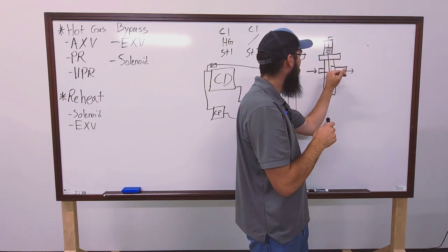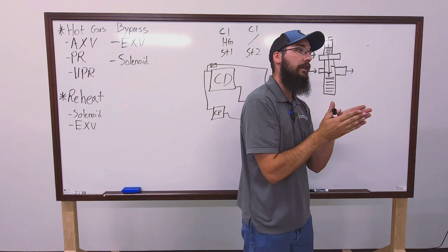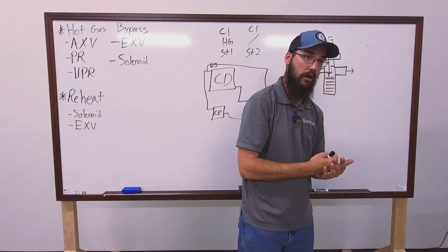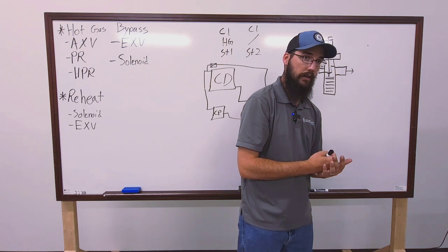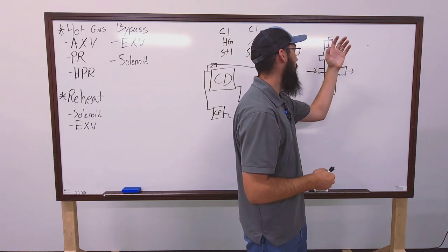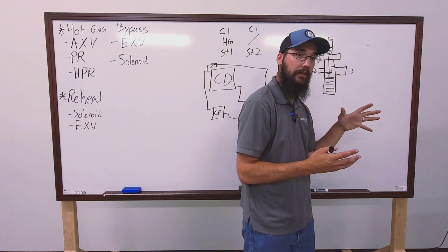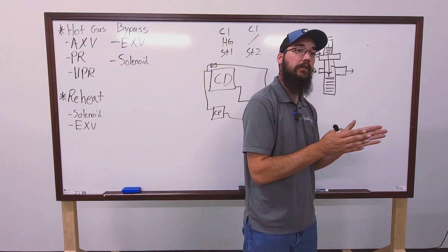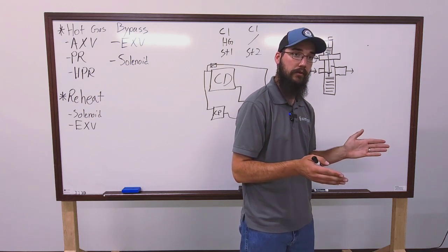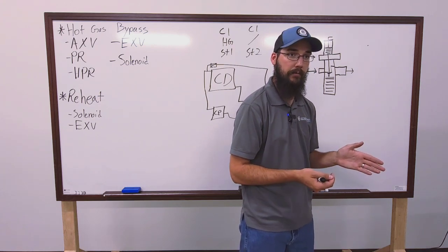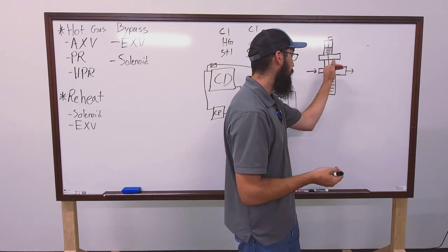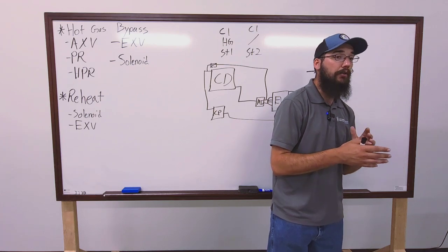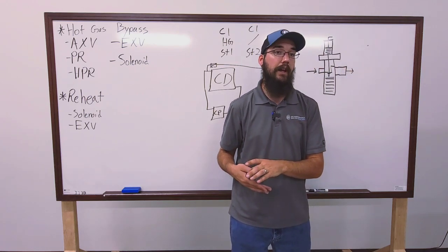So, ultimately, the more you push this down, so the more you thread the adjustment ring in. So, the more you load the springs? Yeah, there you go. The more you load the springs, the higher, or the lower the DP, the pressure differential you'll create across. And, the more you back it off, the more it backs off of that spring seat and allows less flow, which increases pressure differential. Righty, tighty, lefty, loosey. And, that's ultimately what it's doing, is you calibrate this, and you need to be in that low load state. You have to set this in the condition it needs to function in.